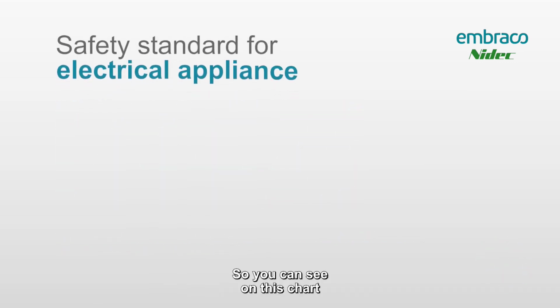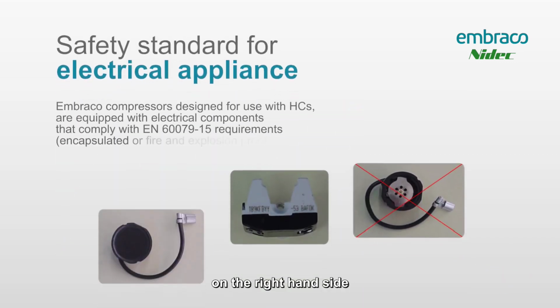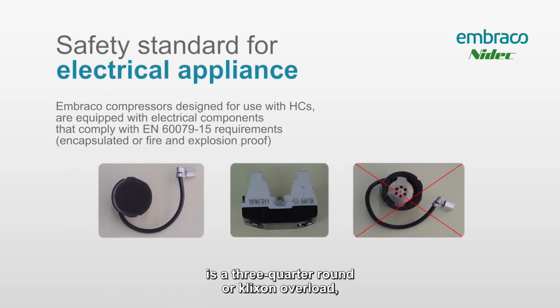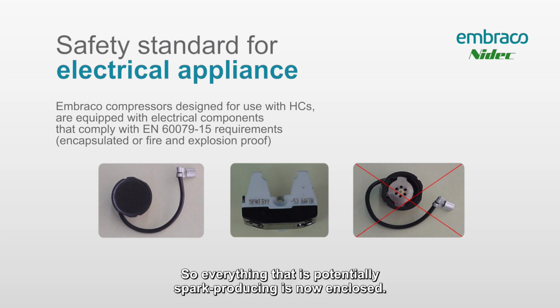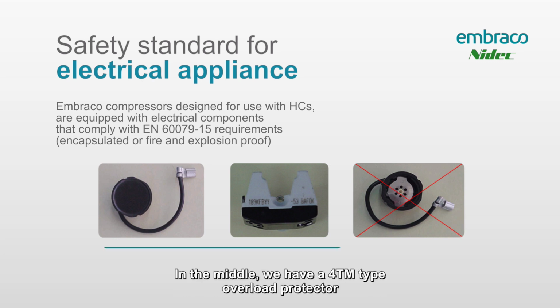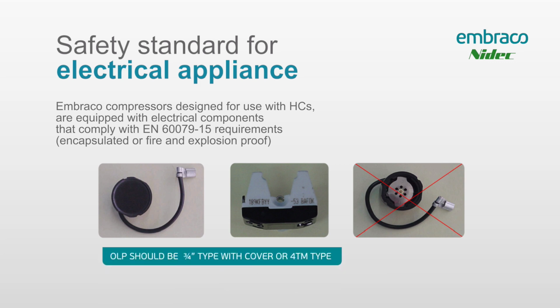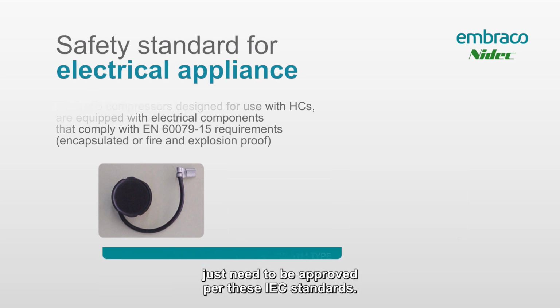So you can see on this chart the difference that I'm talking about. On the right hand side is a 3/4 round or klixon overload, and that's one that will be used on our R134 or 404 compressors. On the left hand side is what a new one's going to look like. So everything that is potentially spark producing is now enclosed. In the middle we have a 4TM type overload protector, and it was already inherently safe. Just needed to be approved per these IEC standards.